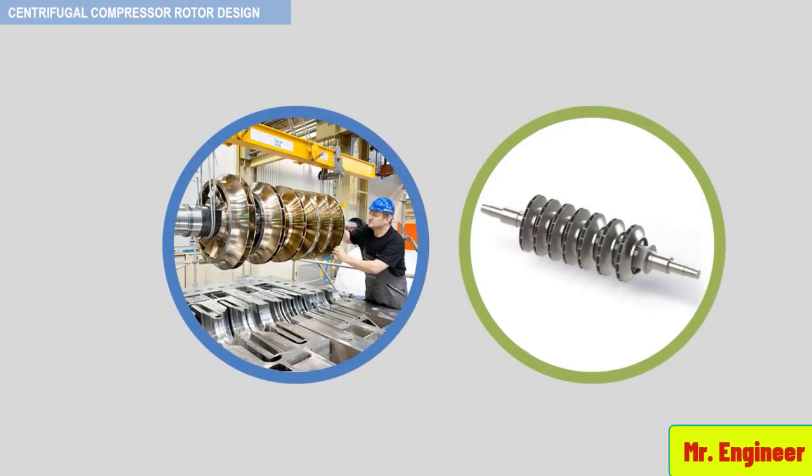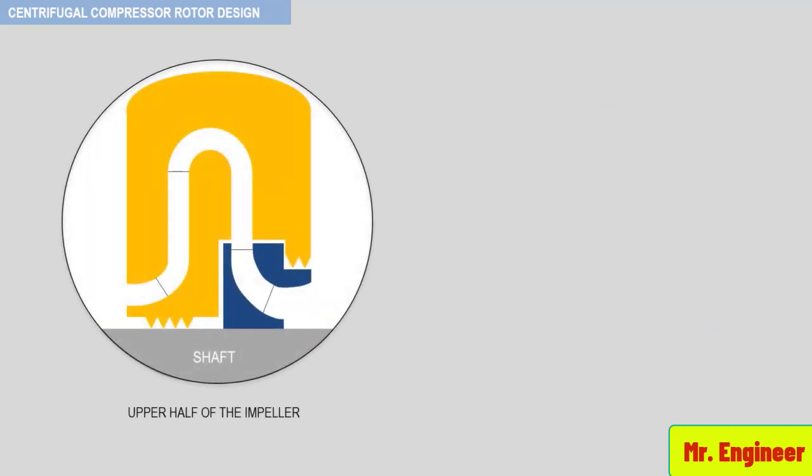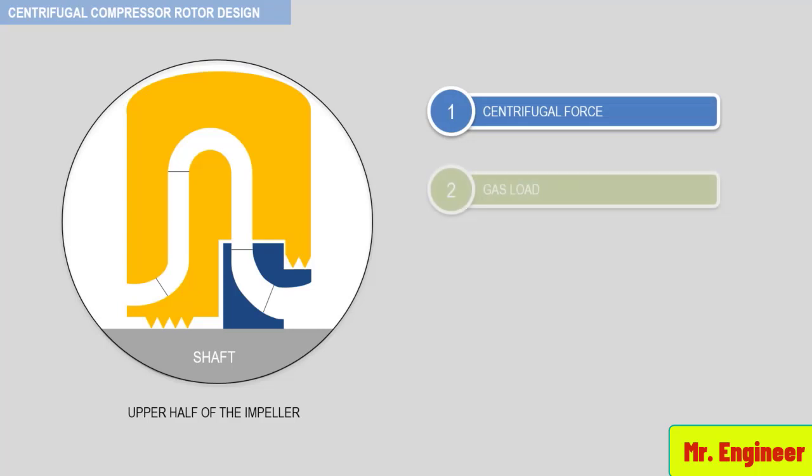All centrifugal compressor rotors are built-up type. That is, the major components are not integral with the shaft and must be shrunk on. So let's see in detail the requirements for impeller shrink fits. The forces acting on an impeller that create impeller stress and require positioning stress or shrink fit are centrifugal force, gas load, the force from the torque.